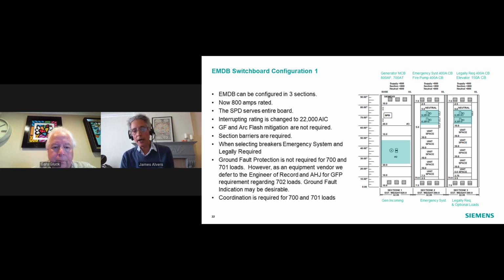Ground fault protection. Okay, here's a caveat on ground fault protection. In the code, it's very specific that it's not required for 700 and 701 loads. However, as an equipment vendor, we defer to the engineer of record and the AHJ for the 702 loads because that wording is not specifically in the 702 section. So we've seen it go both ways. Selective coordination is required for the 700 and the 701 loads. It is not required for the 702 loads.